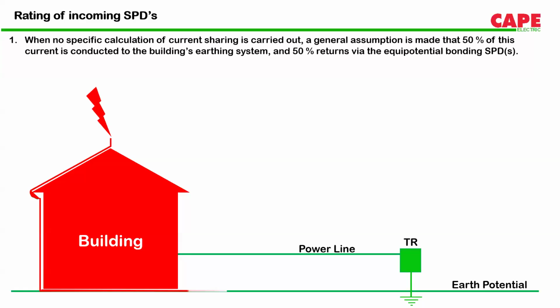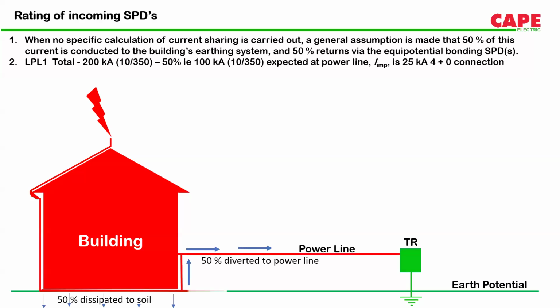But class 1 SPD, what is the minimum impulse current rating? Because if I put 2 kiloampere of impulse current in an SPD, can it be called a class 1 SPD? Can I put 3 kiloampere, 4 kiloampere? What is the minimum rating of impulse current required to call an SPD a class 1 SPD? It is believed, as per standard, that whenever there is a lightning strike, 50% of the lightning energy is dissipated into the ground. The remaining 50% is diverted back to our building through the various metal services coming inside the building.